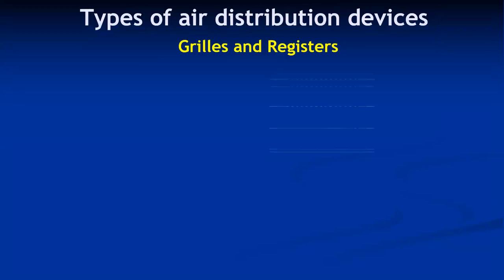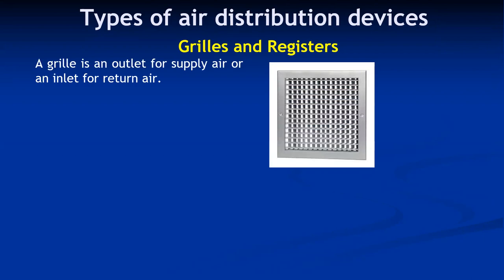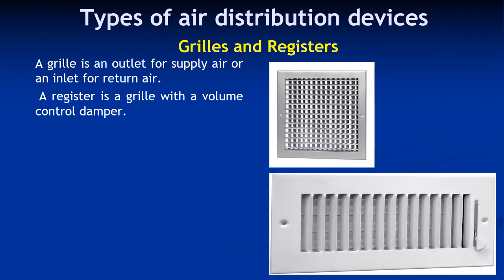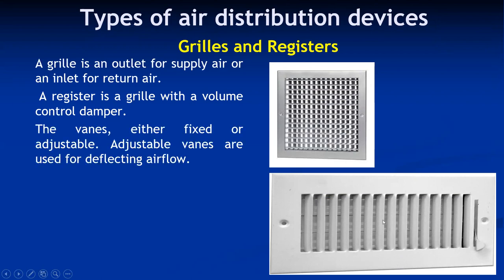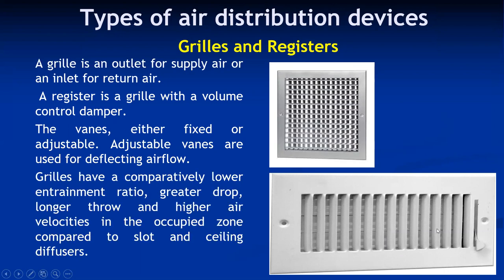The first type is grills and registers. A grill is an outlet for supply air or an inlet for return air — it's like a mesh structure. A register is a grill with a volume-controlled damper. The vanes are either fixed or adjustable; adjustable vanes are used for deflecting the airflow. Grills have a comparatively low entrainment ratio, with a greater drop and longer throw at higher air velocities, lower than that of slot type and ceiling type diffusers.